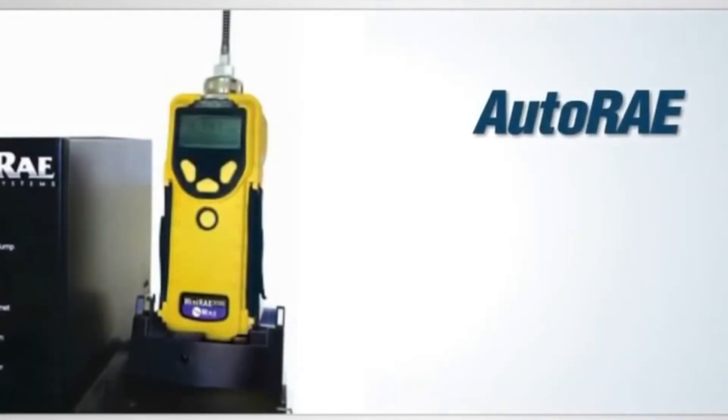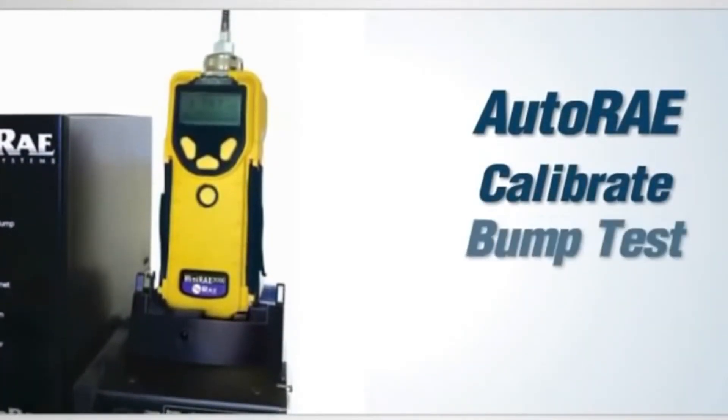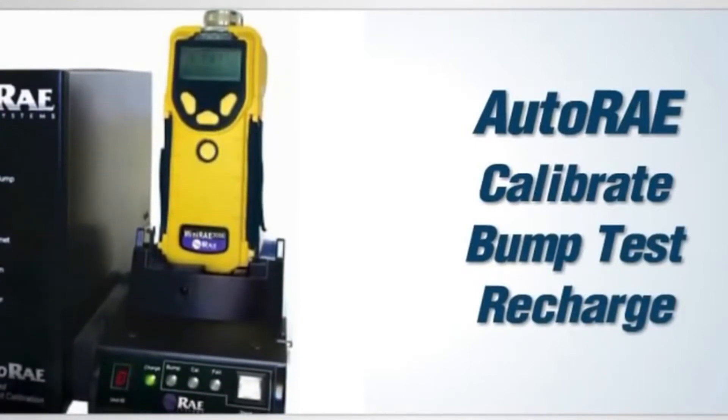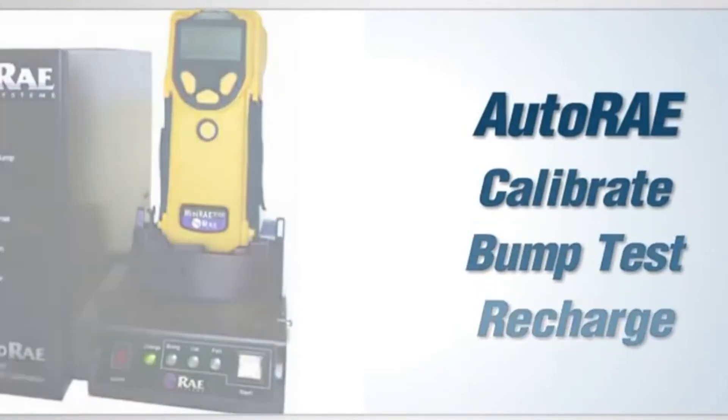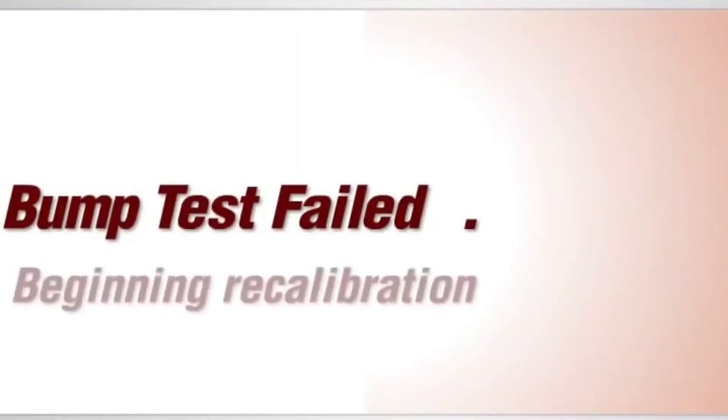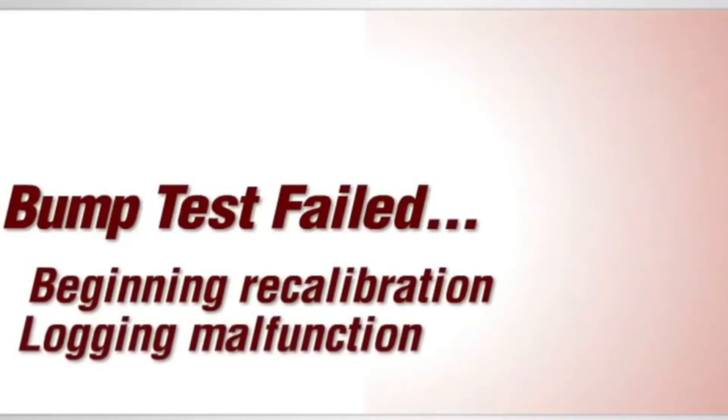The MiniRAE 3000 is compatible with the AutoRAE auto calibration, bump test, and charging system. This docking station informs you of the status of your MiniRAE 3000 sensors. If your MiniRAE 3000 fails the bump test, the system automatically performs a calibration and stores data for documentation.